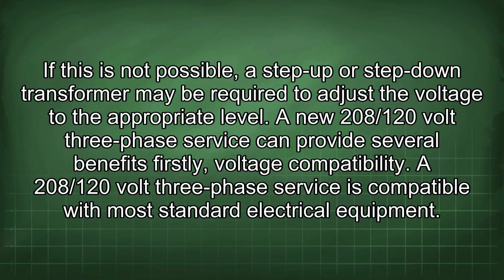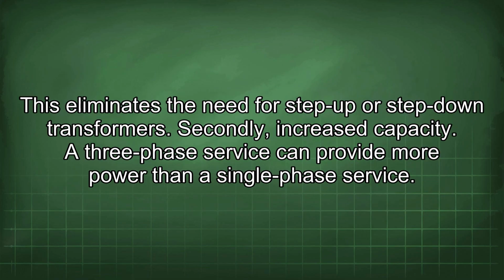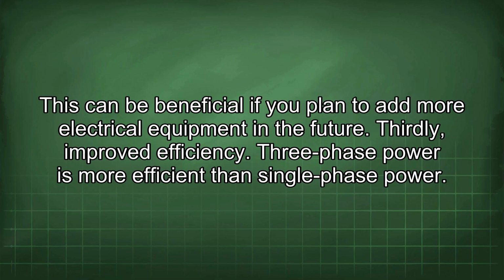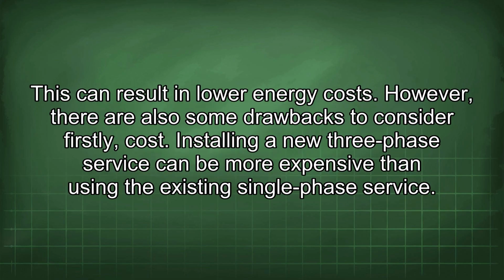A new 208/120 volt three-phase service can provide several benefits. Firstly, voltage compatibility. A 208/120 volt three-phase service is compatible with most standard electrical equipment. This eliminates the need for step-up or step-down transformers. Secondly, increased capacity. A three-phase service can provide more power than a single-phase service. This can be beneficial if you plan to add more electrical equipment in the future. Thirdly, improved efficiency. Three-phase power is more efficient than single-phase power. This can result in lower energy costs.